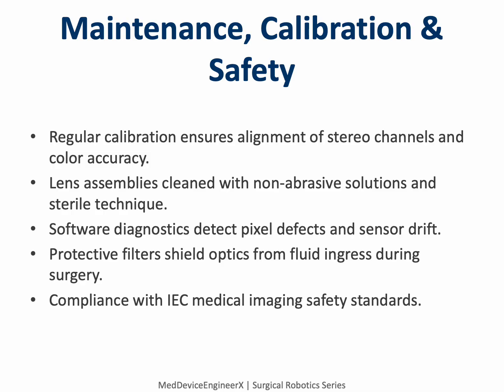Protective filters at the camera tip prevent fogging and fluid ingress, safeguarding delicate lenses. All components meet IEC medical imaging safety standards, ensuring patient and operator protection. Maintenance is designed for simplicity. Technicians can replace or recalibrate modules quickly without removing the tower from service. A well-calibrated vision system isn't just about sharp images, it's about consistent trust in what those images reveal.